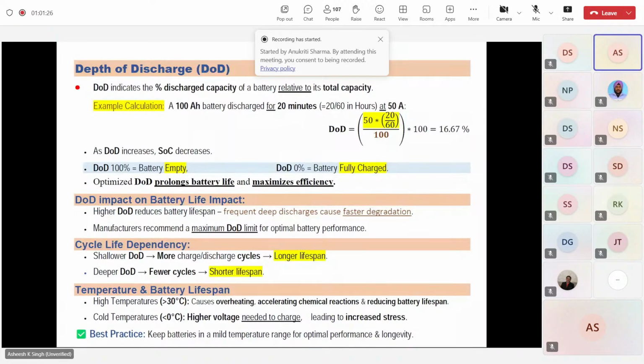Now this depth of discharge, lower value or higher value - there is a difference in impact on battery health. Battery health is related to battery life, or I shall use the word life here, as first life, second life is the terminology we use. Higher DOD reduces battery lifespan, meaning you are discharging to a deeper DOD, which means more time and more current will be required for charging. So these frequent deep discharges cause faster degradation of the battery.